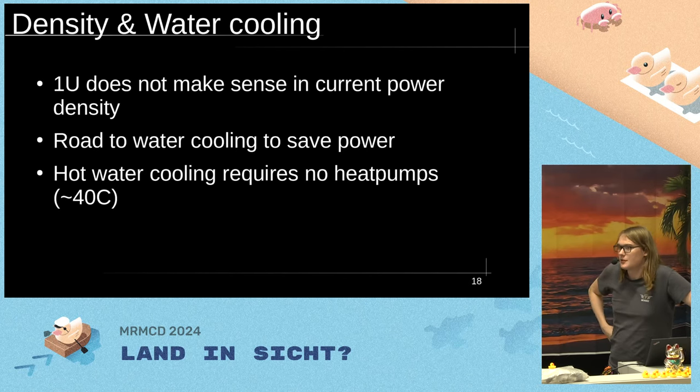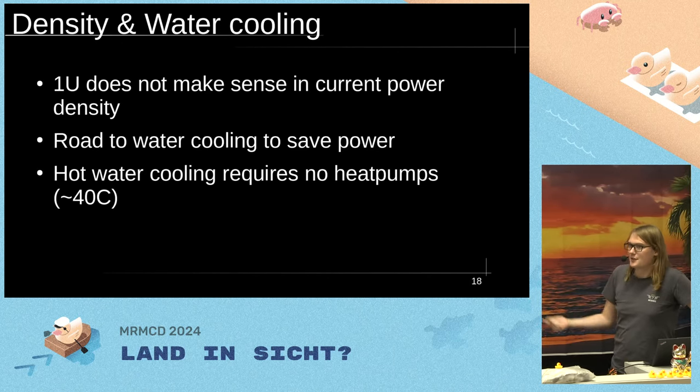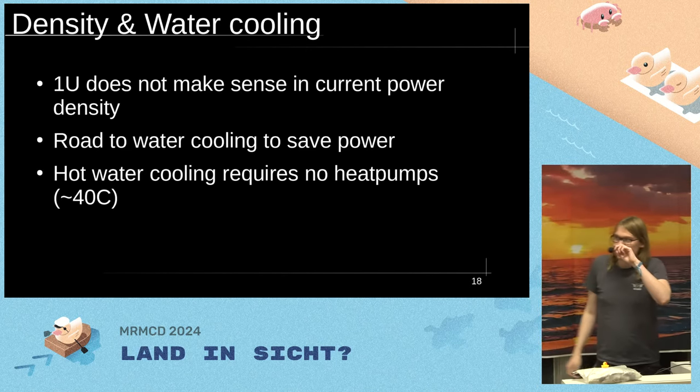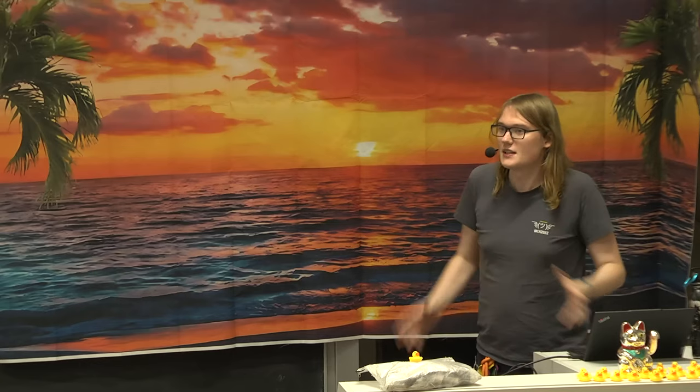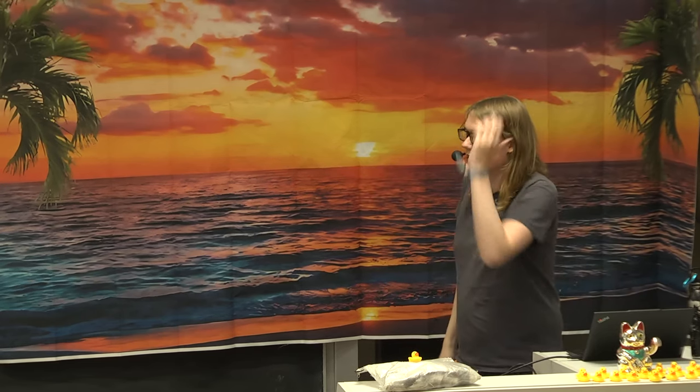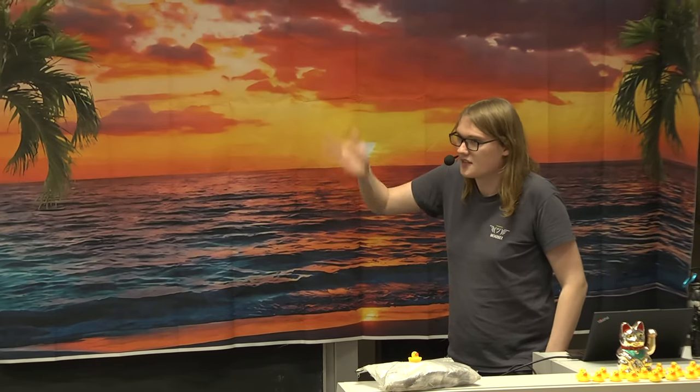The biggest power saving you can make right now is going to water cooling, because you eliminate the fans — that's already 100 to 300 watts saved depending on load. You can even go to hot water cooling, running 40°C water through the servers. Since it's almost never 40°C outside, you can pump the water out to large external radiators, cool it down, and pump it back in. You pump in 40°C water and get 80°C water out — hot enough to use for district heating or other purposes, which is much more useful than getting only 40°C out of 20°C in.